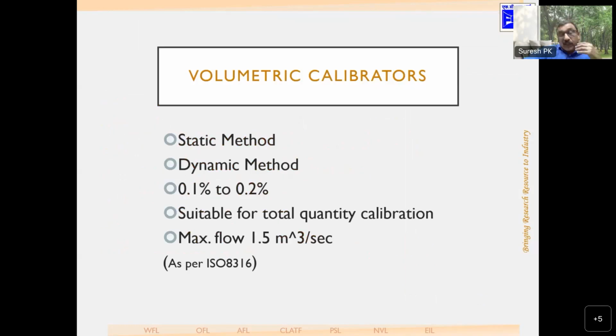Volumetric calibration can be static method or dynamic method. I will explain the static and dynamic later. The accuracies are up to 0.1 to 0.2%. This is suitable for total quantity calibration. The maximum flow rate, due to tank size, is limited to 1.5 meter cube per second.